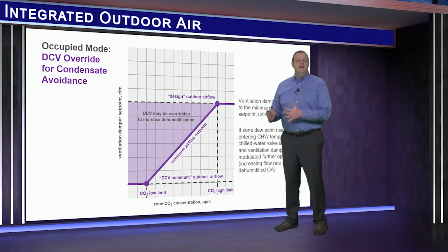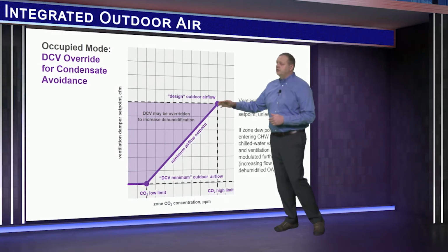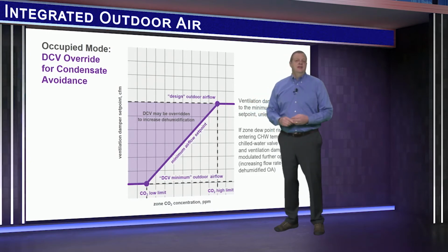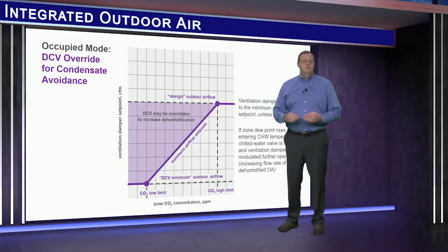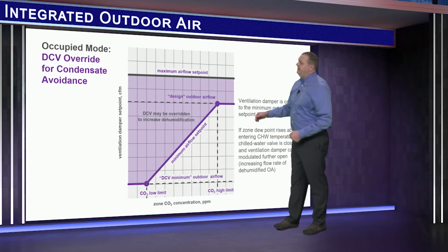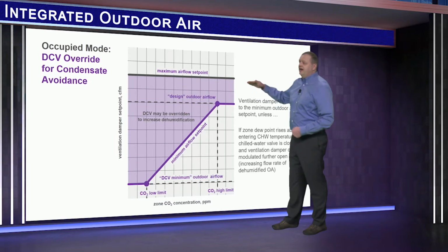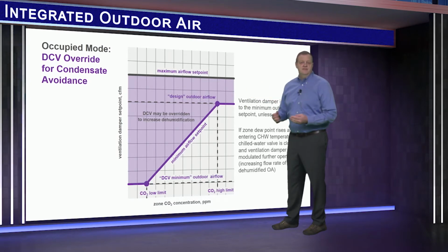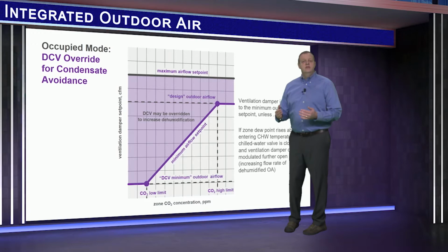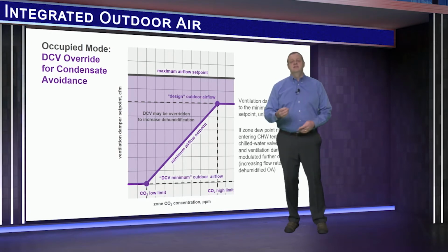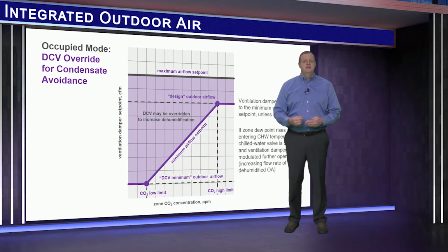This overrides demand control and increases the flow rate of the dry air from the dedicated outdoor system to lower the zone dew point. Then the chill water valve will be allowed to open again. Now this ventilation damper has a separate maximum airflow set point, which can be set even higher than the design outdoor airflow if desired. Just like the cooling boost mode, this gives you the flexibility to provide a boost of dehumidification to a zone where the latent load might be higher than you estimate.